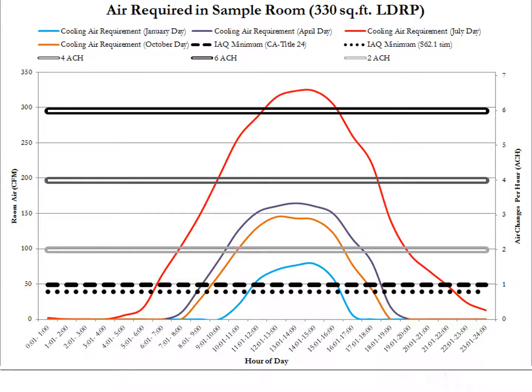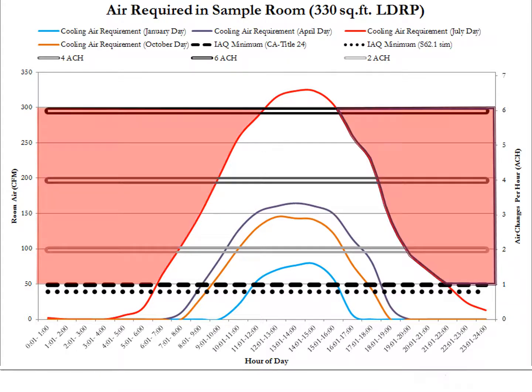You can see that on a summer afternoon, that's an appropriate ventilation rate—we want that much ventilation then. The rest of the time, it overventilates the room, because the code sets the minimum ventilation rate, or turn-down position, for how much air you have to use at night during economizer hours when the patient is asleep. In those areas, we're overdoing it by a lot.